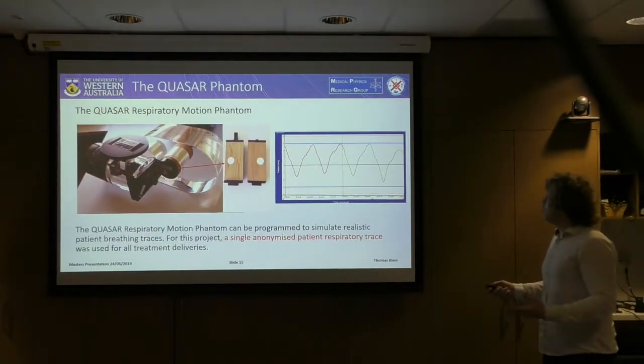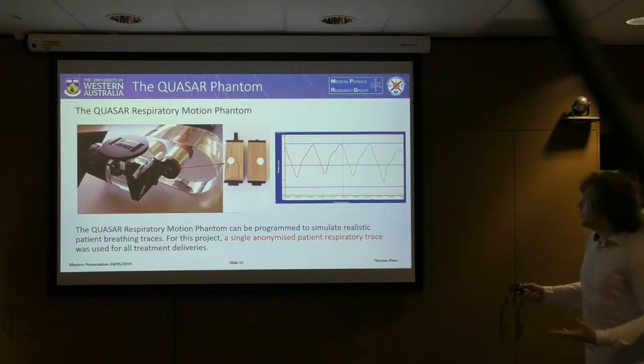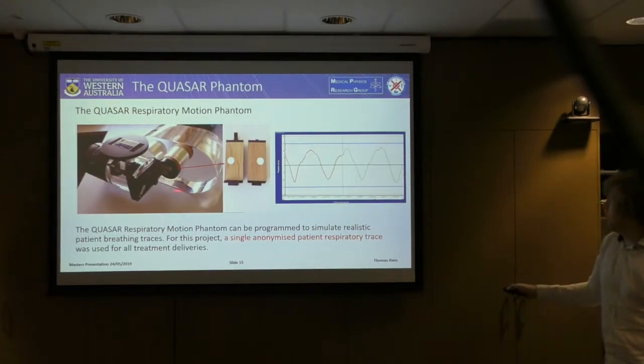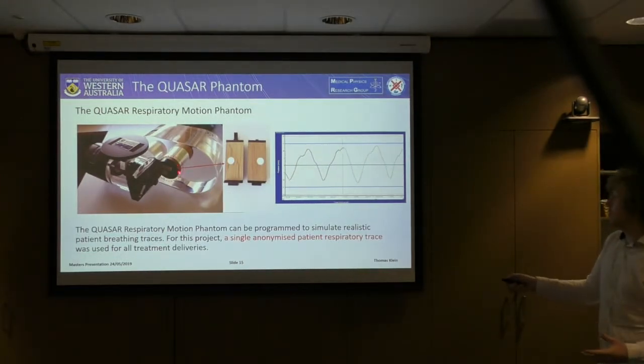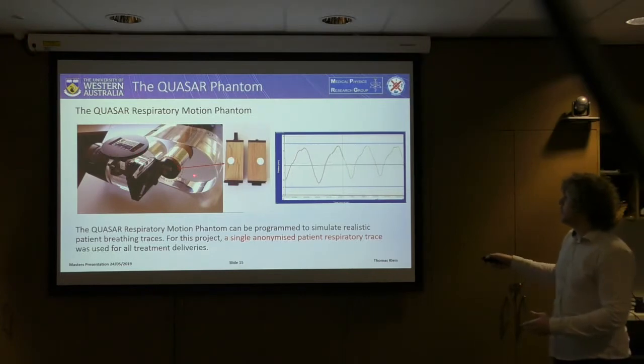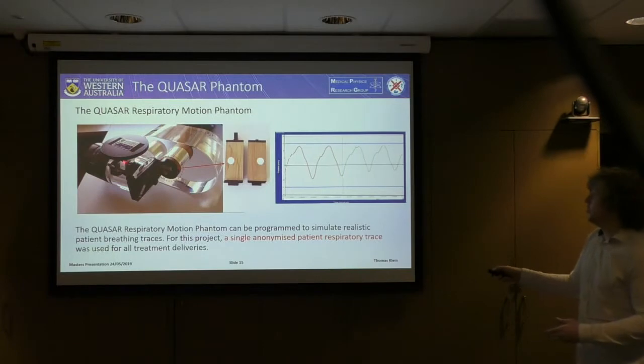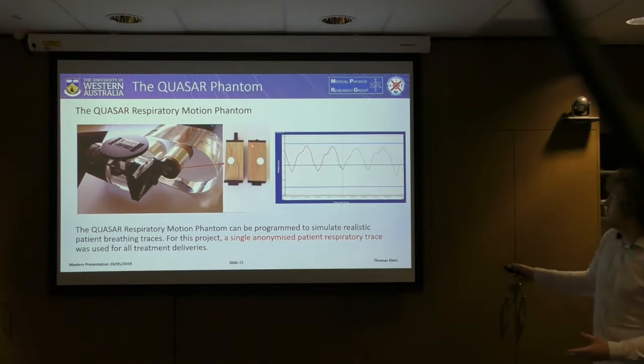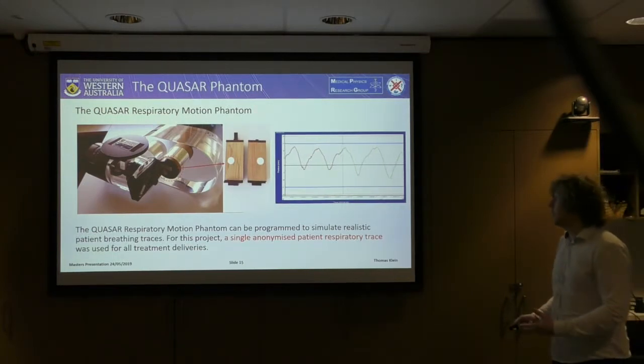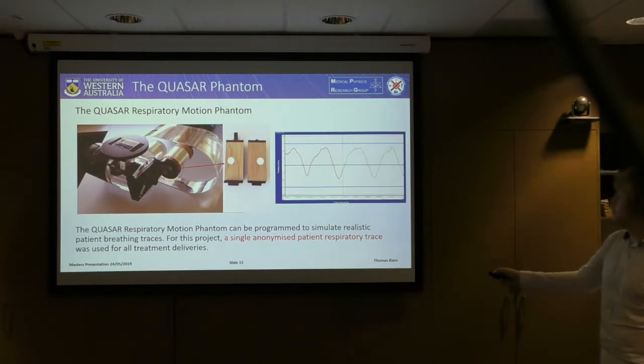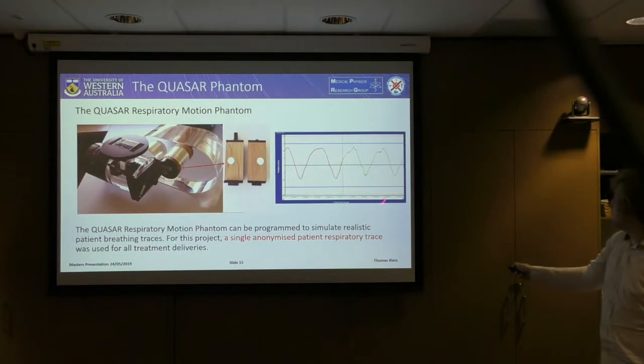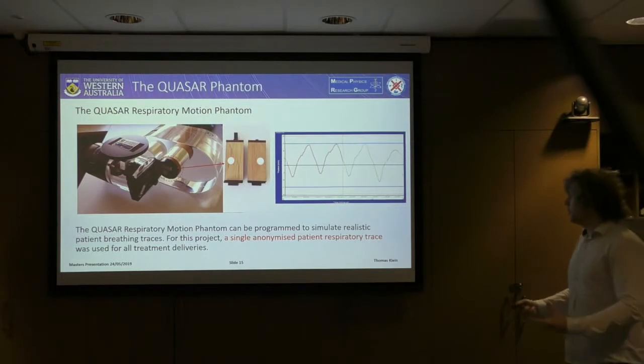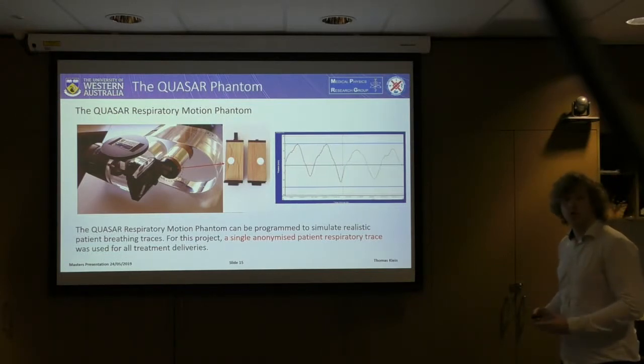For all treatments, we used the Quasar Respiratory Motion phantom. This phantom comes with a body to simulate the patient torso and space for two inserts — one for the surrogate lung and one for the driving motor. The surrogate lung allows measurement of dose in the central 2D plane, and the motor can be programmed with real patient respiratory data to replicate real patient respiratory motion. For this project, we used a single anonymised patient respiratory trace for all treatment deliveries.